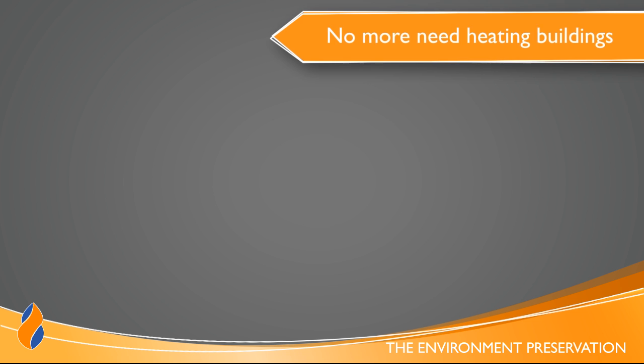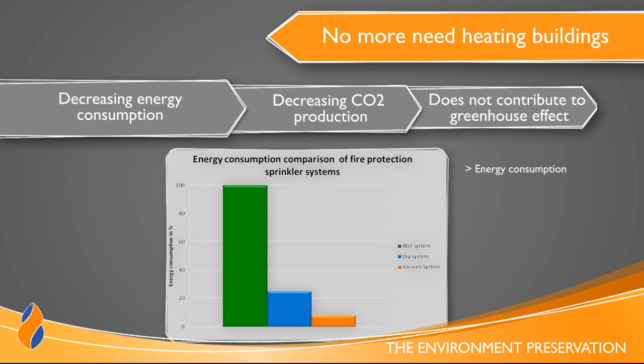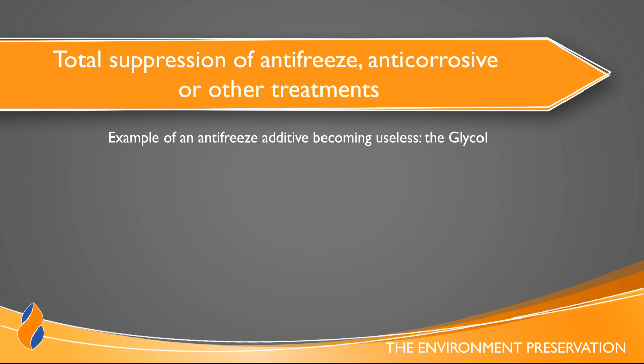With the VACTEC system, there is no more need for heating buildings. Frost protection of buildings that are secured by wet sprinklers requires heating during an average of 5 months, whereas the VACTEC vacuum system does not need heating. Therefore, it allows then a significant reduction of energy consumption and does not contribute to the greenhouse effect. Finally, the VACTEC system totally eliminates the need of using antifreeze and anti-corrosive treatments.